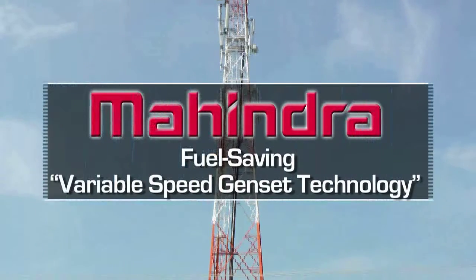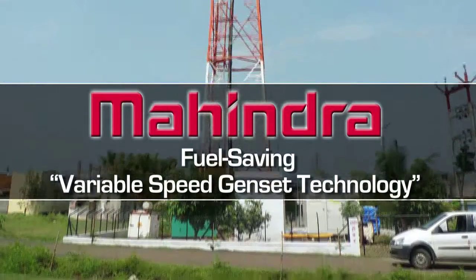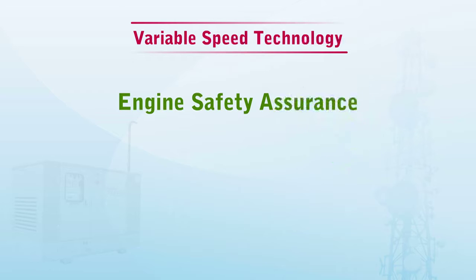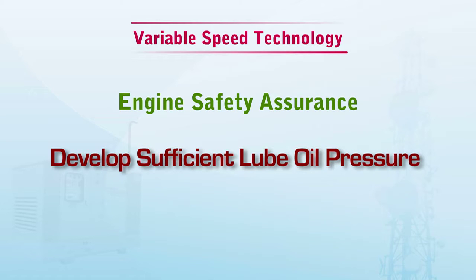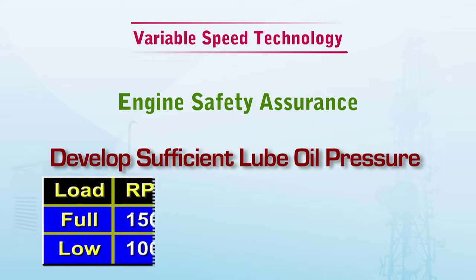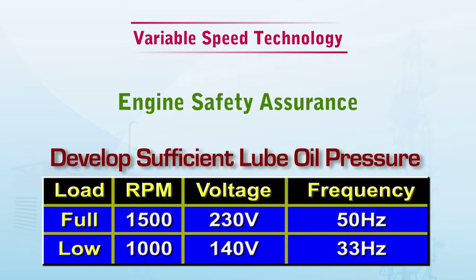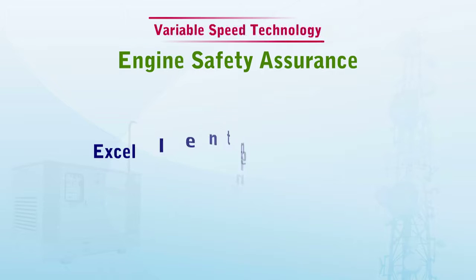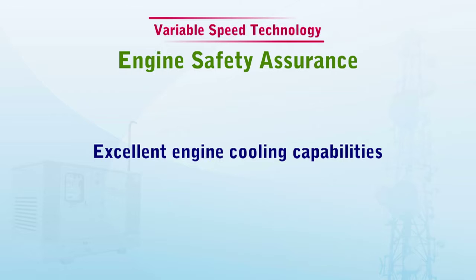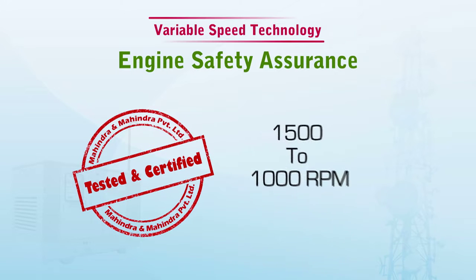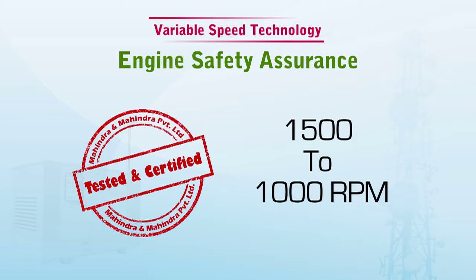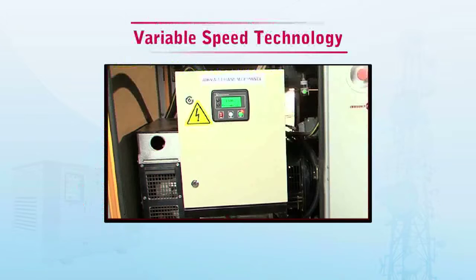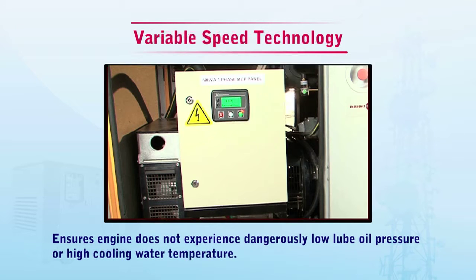In addition, Mahindra & Mahindra has tested in-field conditions and validated that all Powerol engines develop sufficient lube oil pressure in the entire variable speed operating range from 1000 to 1500 RPM and also have excellent engine cooling capabilities. As a result, the variable speed range of 1000 to 1500 rpm is certified to be safe for the engine's operation. In summary, the new engine control panel always ensures that the engine does not experience dangerously low lube oil pressure or dangerously high cooling water temperature.